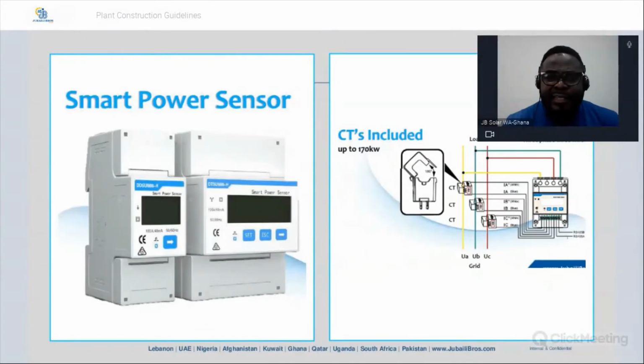Remember, as a caution, the Huawei Smart Power Sensor can only be used for systems up to 170 kilowatts. Take note, if you are doing any system above 170 kilowatts, unfortunately you cannot purchase a Huawei Smart Power Sensor for your job. Take note of this point clearly. So say you have a 300 kilowatt project that you are doing, and you have bought Huawei inverters — you cannot purchase this Huawei Smart Power Sensor for that job.